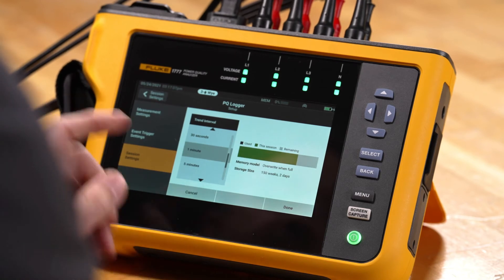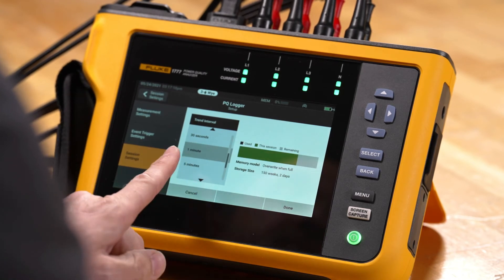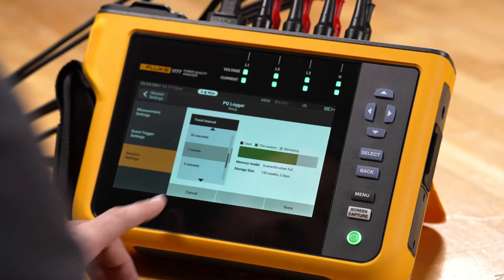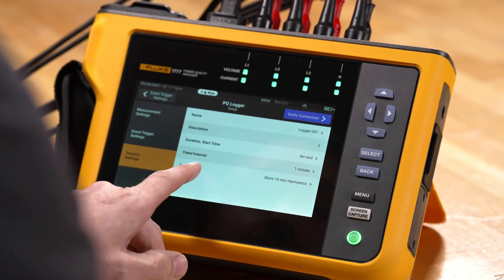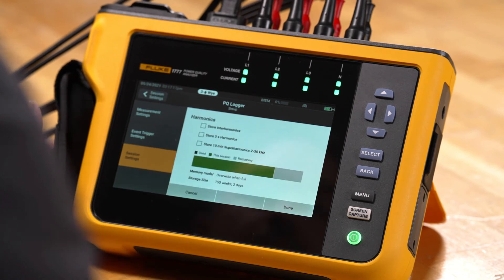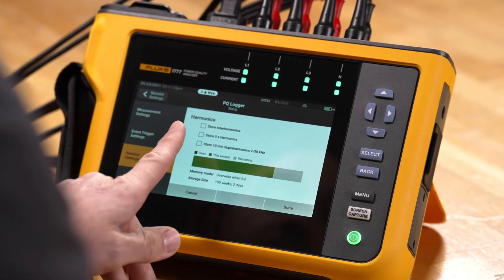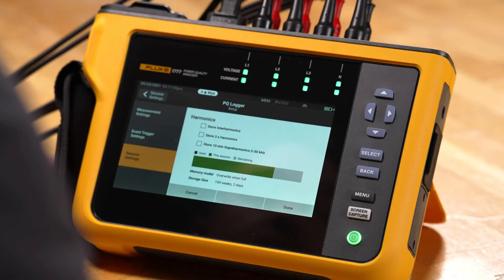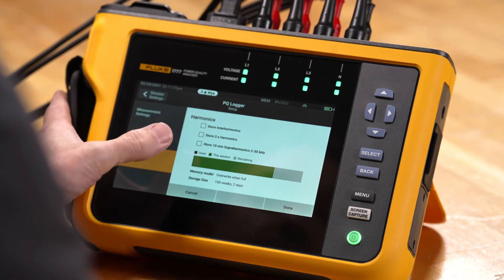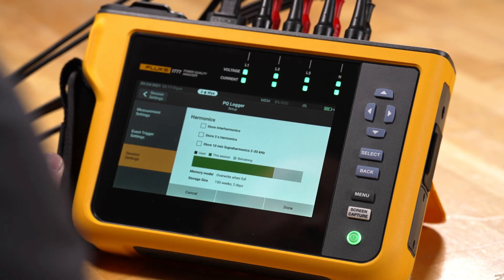It's important to note that trend interval doesn't have anything to do with your event capture — events are still captured when they happen. We also have an option here for harmonics. For harmonics setup we can store interharmonics, we can do three-second harmonic data which would be for IEEE 519 purposes, and we can also store 10-minute supraharmonics which are 2 to 30 kilohertz harmonic frequencies. Once we pick these, it'll show us how much memory consumption is taking place from those parameters, letting us know the maximum record time.